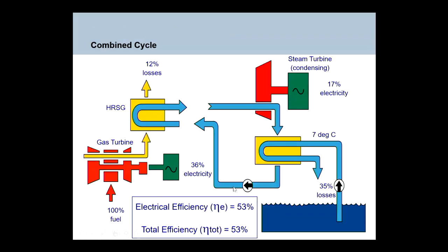Combined cycle is more complex, so I have a gas turbine. The air is drawn in, burnt with fuel, exhausted, but in this case exhausted through a boiler, a HRSG, where we're turning water into steam. We expand the steam through a steam turbine. Again, I've got a condenser and I've got losses into the condenser, but I'm producing, for 100% fuel, say 17% out of the steam turbine generator and 36% out of the gas turbine. Now I'm at 53% efficiency.